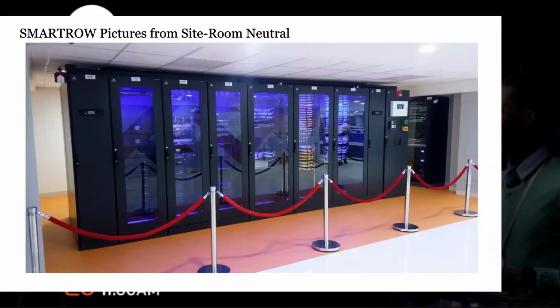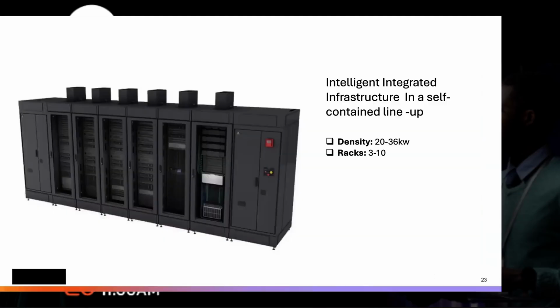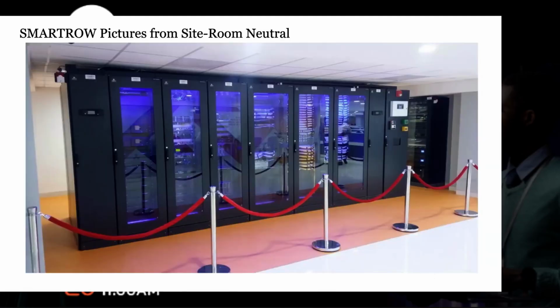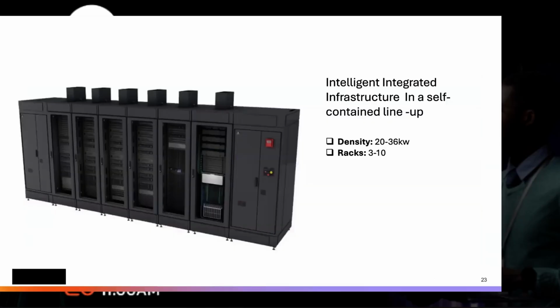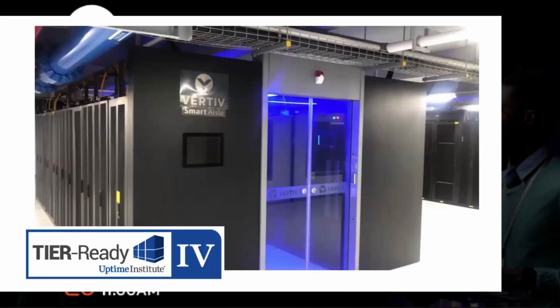This is a typical one we deploy for a customer. You can see how the smart row is arranged. In the smart row, we can have a density of 20 to 30 kilowatts, and you can have up to 3 to 10 racks in a row. This is pre-engineered and designed.